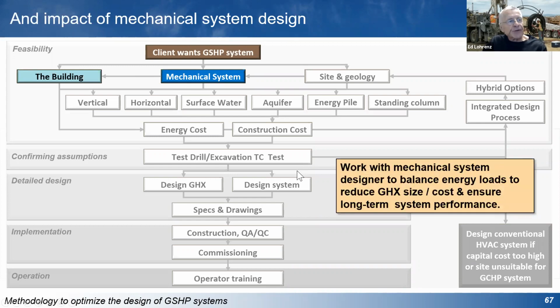What happens if you use an energy recovery ventilation system of a certain efficiency, or what happens if you control the ventilation with CO2 monitors or whatever else? Anything you can do to balance the loads is going to reduce the size and the cost of the ground heat exchanger.